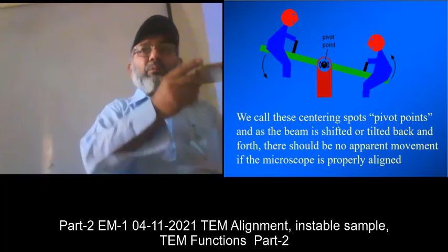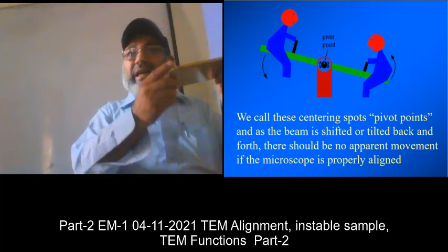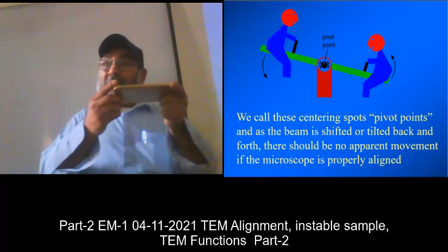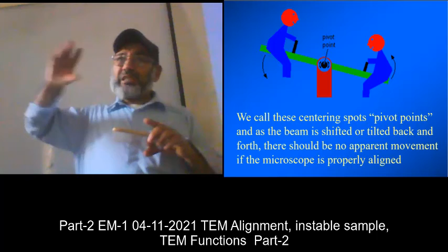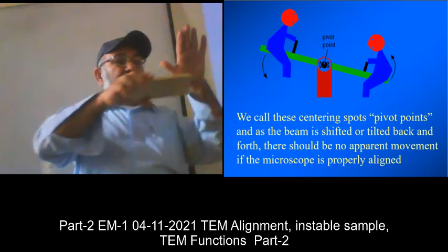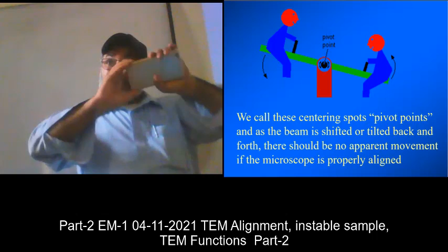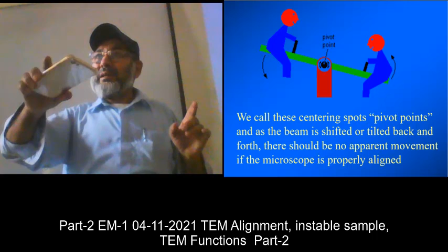When you move the goniometer and the sample is moving like this, it is correct. But when I move it like this and it shifts, this means there is some problem in alignment. So when I focus everything, then I move the goniometer. The goniometer is basically, this is the sample holder, and here outside you have the goniometer. When you move the goniometer, you are actually tilting the sample. And if this tilting doesn't change the position, but it is tilting at the same position, then we say that you have achieved the eucentric height of the sample.